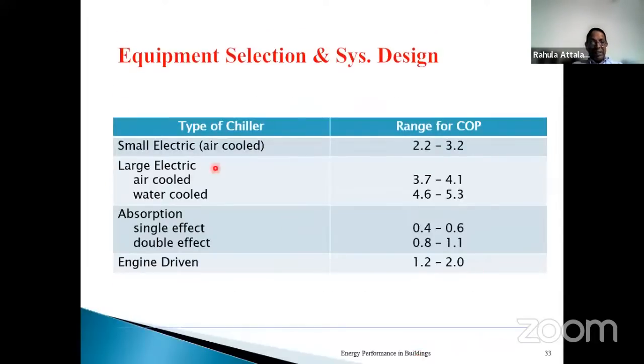This will indicate, for different types of chillers, small electric chillers, large electric chillers, air-cooled, water-cooled, what the COP value is. You see that water-cooled chillers have a higher COP value than air-cooled chillers, and larger chillers have a better efficiency or COP than smaller chillers. This is something that I have indicated. This is for a special case where chillers are driven by engine. And this is another, different type of air conditioning system called absorption air conditioning, which is different from the electric vapor compression based air conditioning.